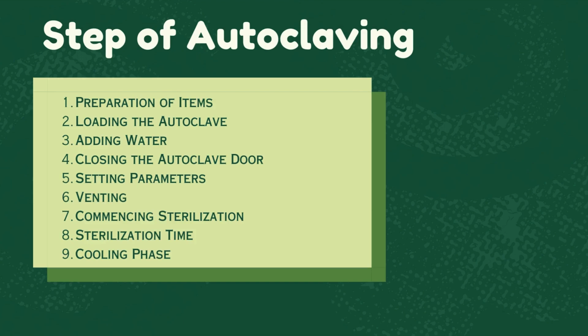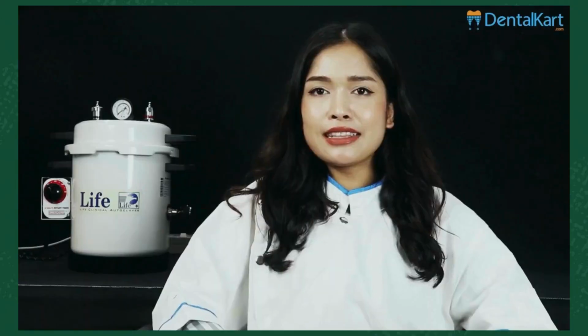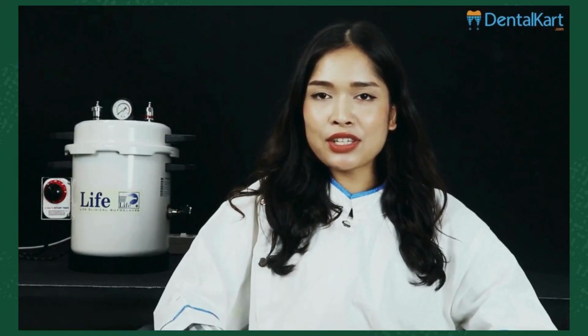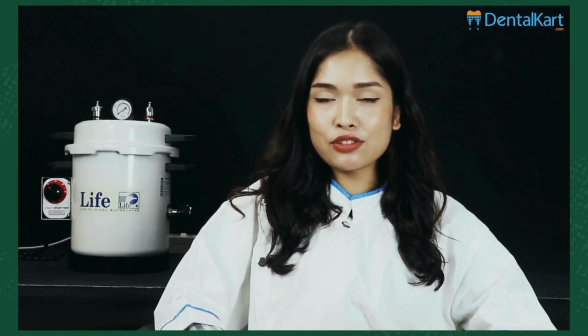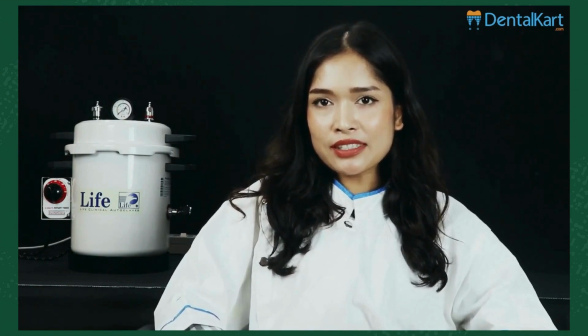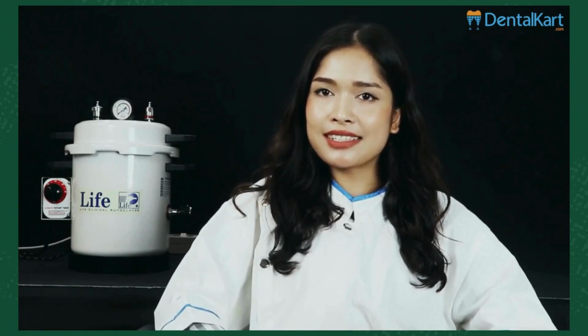Reminder: always follow the specific guidelines provided by the autoclave manufacturer and any protocols established in your laboratory or facility. It's important to ensure the safety of both the operator and the items being autoclaved. In the next slides, we will show you a video of how autoclaving is done. This video is about the basic sterilization equipment most commonly used, the top loading autoclave. We're going to discuss its working principle, parts, directions to use, and potential hazards.